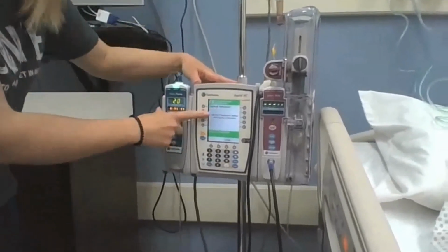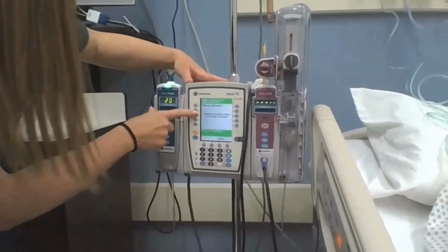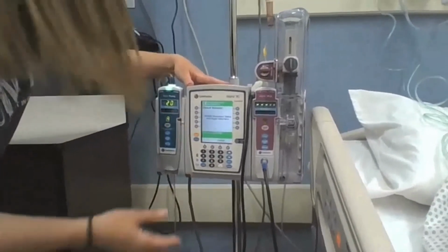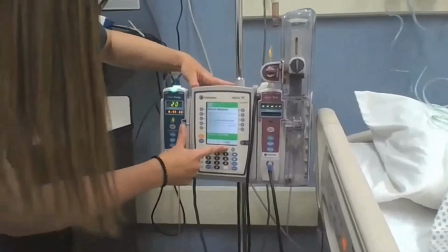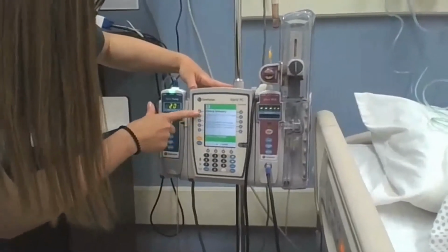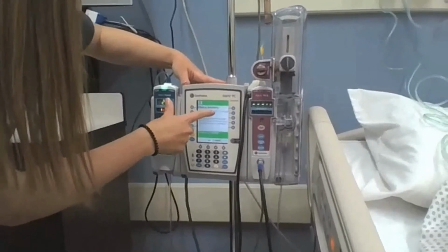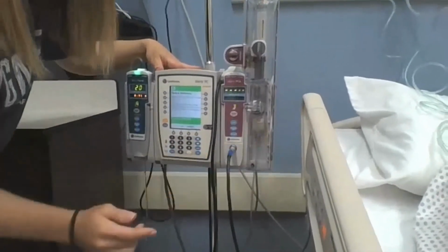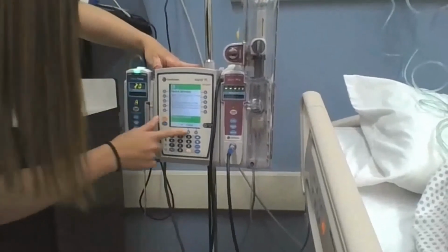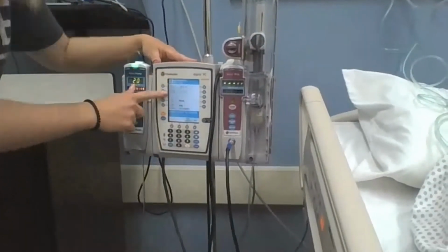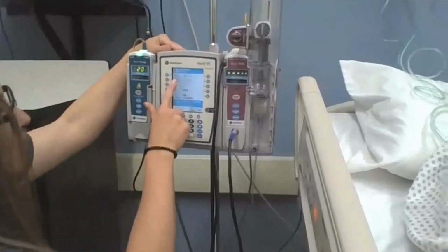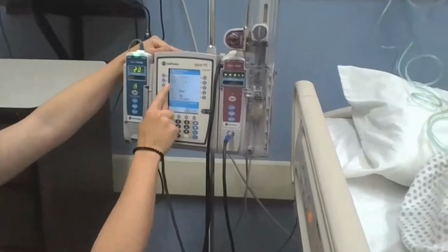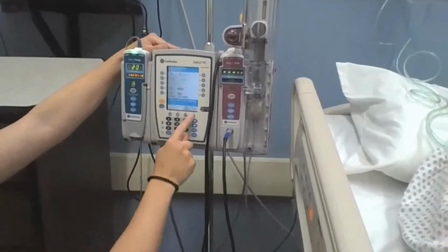And then it gives me a clinical advisory, which says to monitor the respiratory status and O2 saturation, which we do at MMH by doing continuous SpO2 monitoring and the CO2 monitoring. I'm going to confirm that. It says to attach the end-tidal CO2 module now, and that would be the yellow one that's required over here next to your PCA pump at the hospital. And then this is asking me to confirm my drug amount.